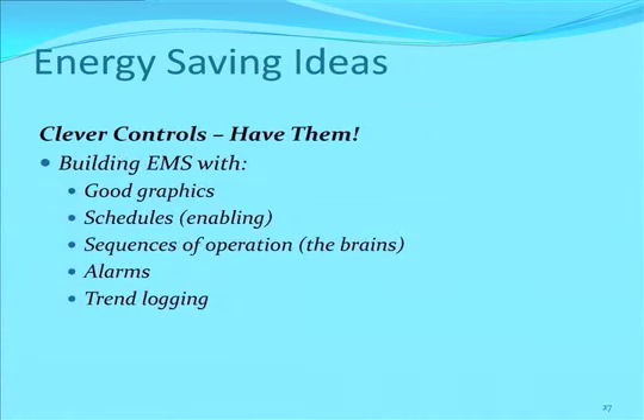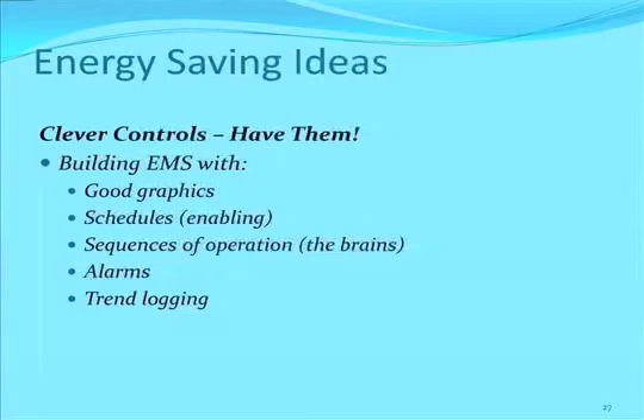So have a building energy management system, one with good graphics. By good graphics, I mean a very intuitive schematic, and also clear information on the flows and the operation of everything. Schedules that enable the equipment to run when it should be during occupied times, and then also sequences of operations, the real brains of things. Have it be clear. For example, the staging of your cooling tower, that your spray pumps go on first, and then you start either staging your fans on or running your variable speed drive up to it.